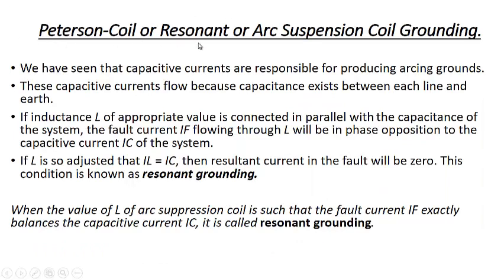The last one is the Peterson coil or resonant arc suppression coil grounding. It is, we can say, similar to reactance grounding, but the value of the inductance is variable. We have seen the capacitive currents are responsible for producing the arcing grounds. These capacitive currents flow because capacitance exists between each line and the earth. If an inductance L of appropriate value is connected in parallel with the capacitance, the fault current IF flowing through L will be in phase opposition to the capacitive current IC, as we have seen already in the case of inductive circuits. If L is adjusted so that IL is equal to IC, then the resultant fault current will be 0. In the previous case, it was not exactly 0, but IC had decreased because of the presence of IL or part of it.